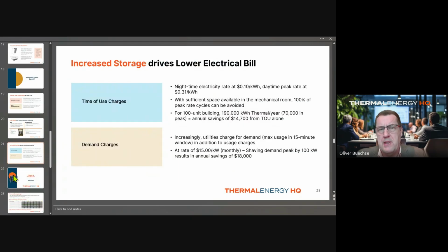Another angle here is really driving down the electrical bill. There are a lot of nuances to this: what is the energy pricing in your local market, are there time-of-use rate cycles, are there demand charges? As an illustration, if you have a delta between your nighttime electricity rate and your daytime rate—we've used about a 3-to-1 ratio, though we've seen far greater discrepancies in some markets and tariffs—the ability to charge the tank during off-peak cycles and utilize the energy throughout the day results in a significant economic benefit.